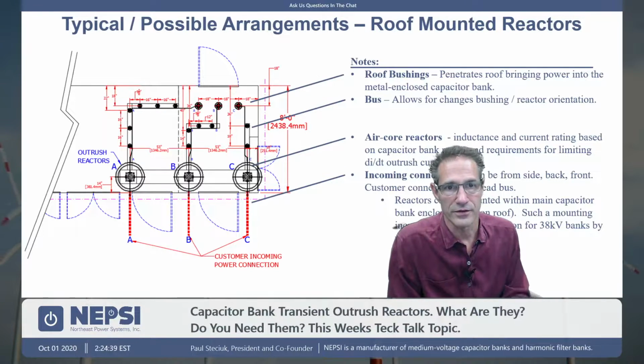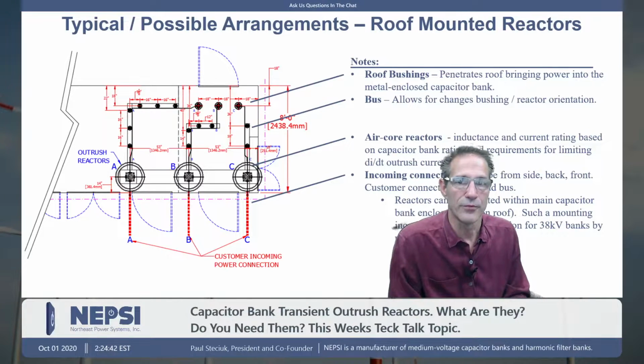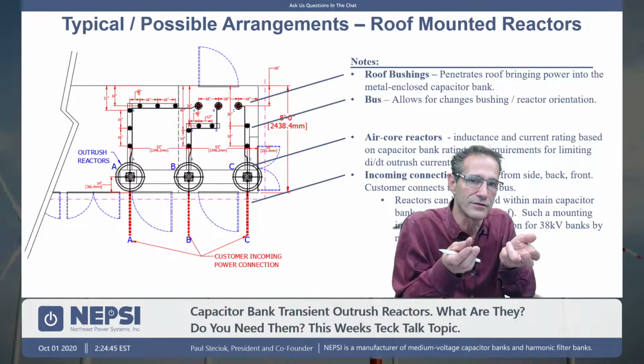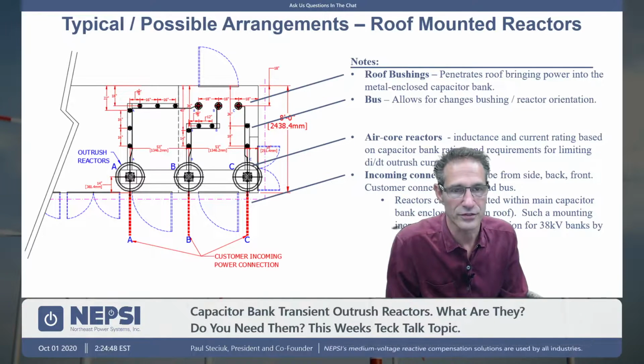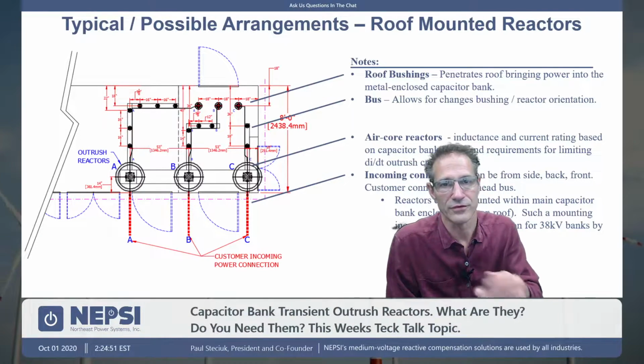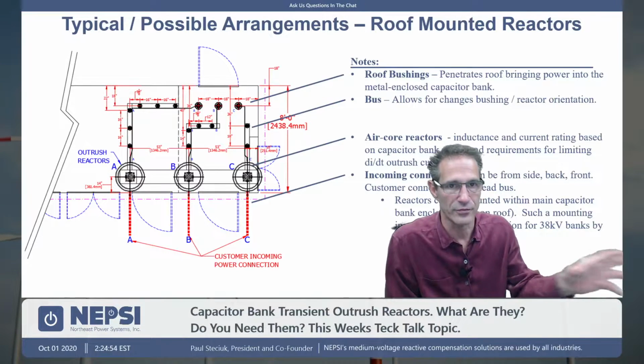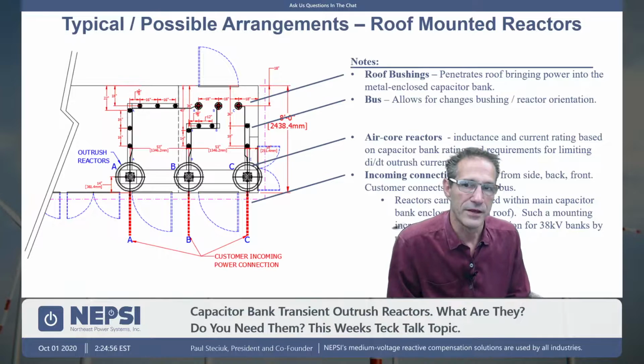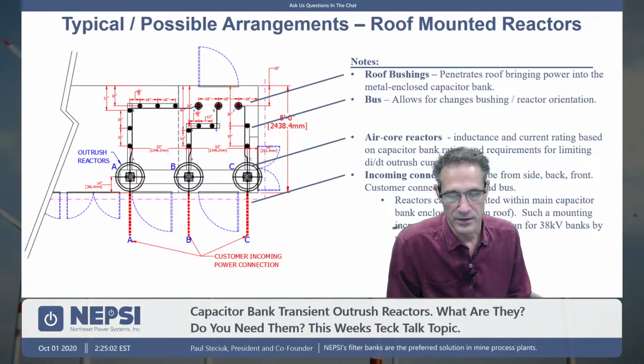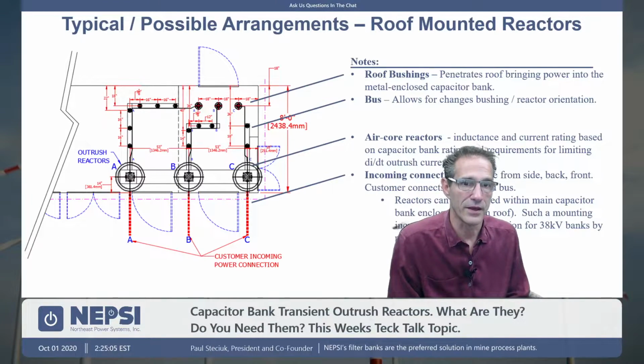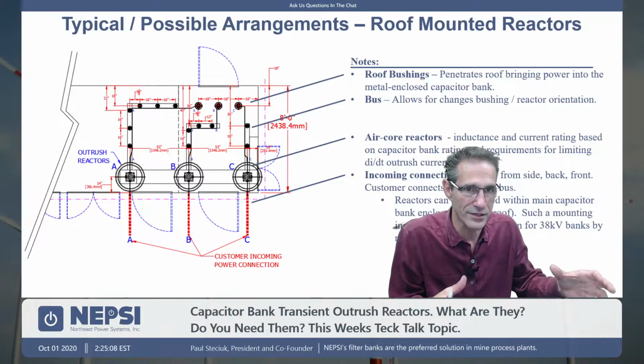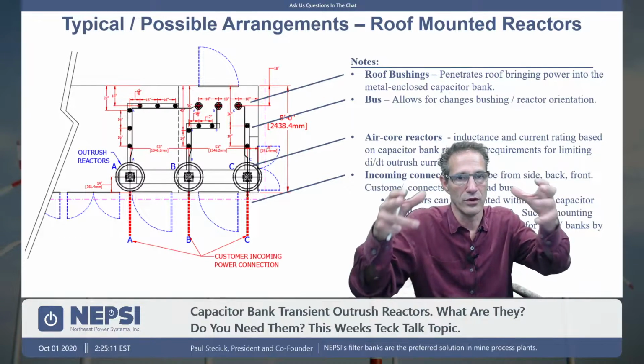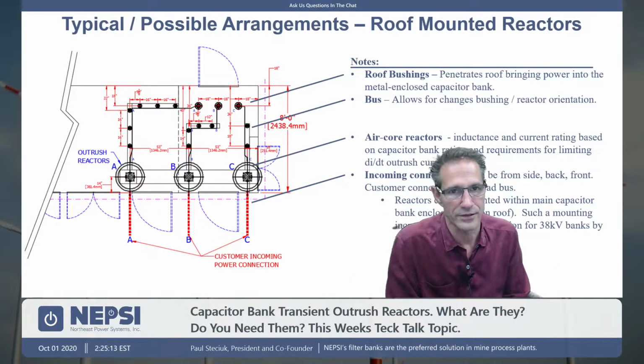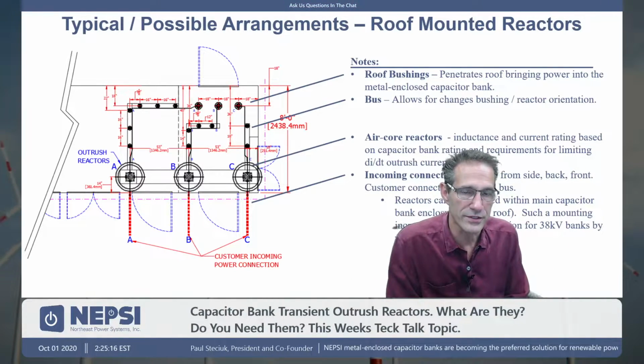There is a thought, and what Christian has just noted here is that perhaps I can increase the inductance of the transient inrush reactors to a value that also solves the outrush issue for the feeder breakers within the substation. And the answer is we have sometimes seen that to be effective. You have to think about, if you have a three-stage bank, I get one third of the total current in each of the stages, or I can put one large reactor on the output. So I think it's a good question. I think you have to do the economics, and we sometimes will.